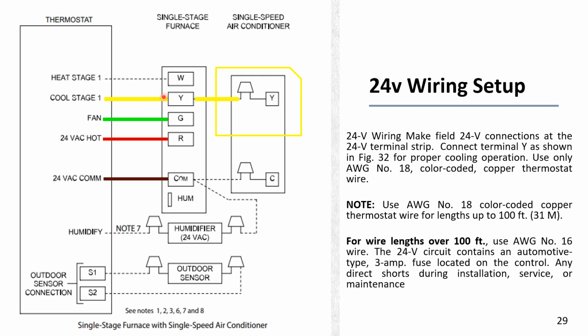The wiring is exactly the same. Yellow for the contactor for the condensing unit, and then you have the same thing as you always would have. Whites for heat. Green is the fan. Sometimes they use gray for the fan, and then you have red for your hot, and then brown common, or sometimes you can use the blue. But the main thing right here is anything under 18 gauge, do not use it. Use 18 gauge conductors. And if your wire length is over 100 foot, make sure you're using 16 gauge.